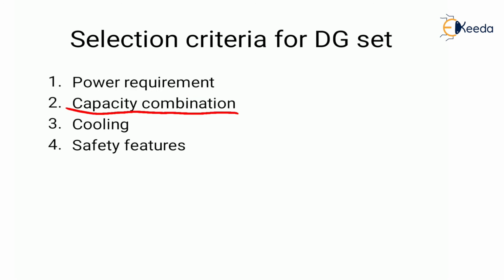Next is capacity combination. From the point of view of space, operation, maintenance, and initial capital investment, it is certainly economical to go for one large DG set rather than two or more DG sets in parallel. Running two or more DG sets in parallel can be advantageous, as any shortfall in the power, depending upon the extent of the power cut prevailing, needs to be filled up. Also, flexibility of operation is increased since one DG set can be stopped while the other DG set is generating at least 50% of the power requirement. Another advantage is that one DG set can become 100% standby during the lean or low power cut period.